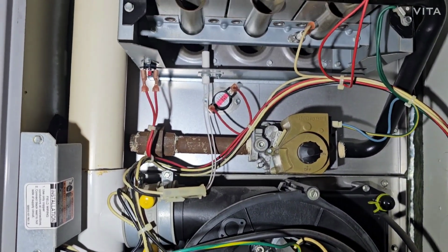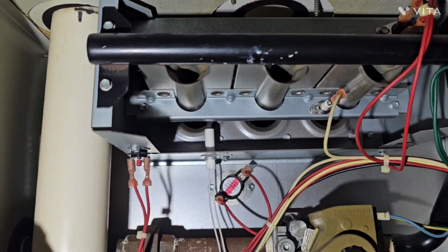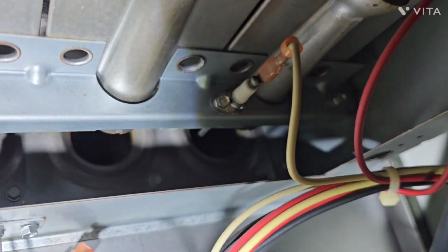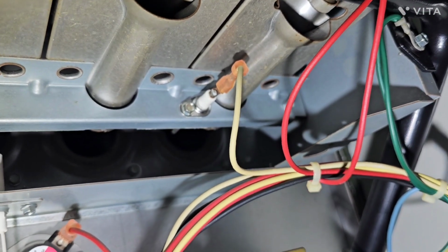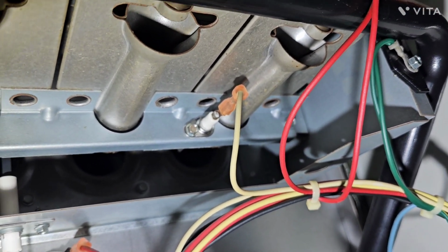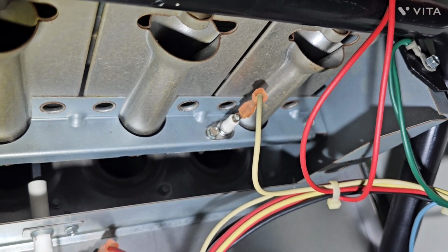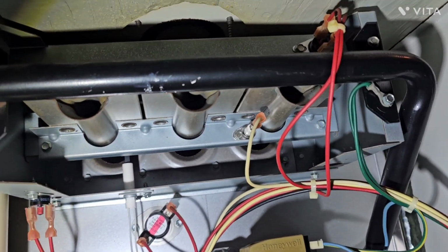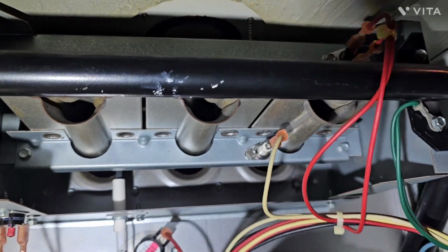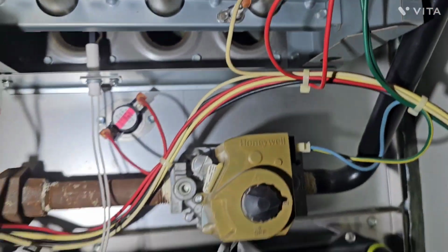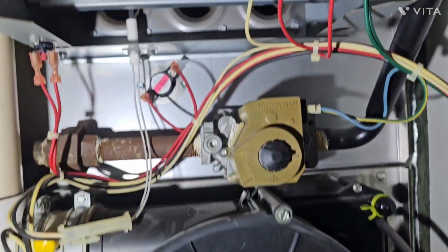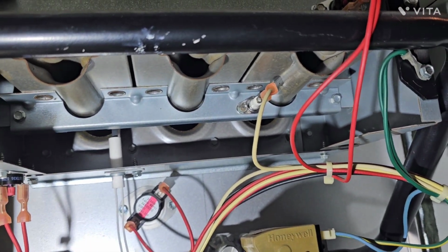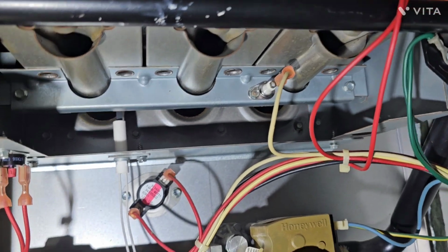There are a couple other things that can go wrong in mid and high efficient systems. They have a flame sensor that goes out here. That's this piece right here. Basically, when the flame starts up, it has about 5 to 20 seconds to prove to the gas burner that there's heat there. So it sends a signal back to the gas valve, or the computer in this case, that there is heat, so you can keep the gas valve open.